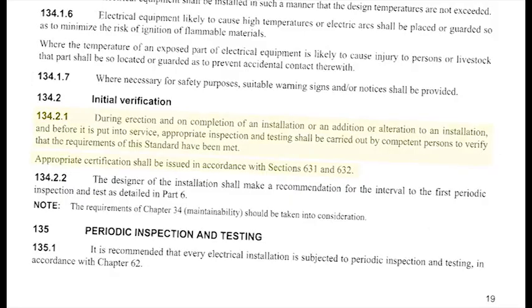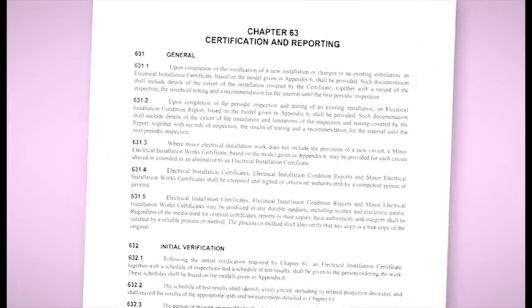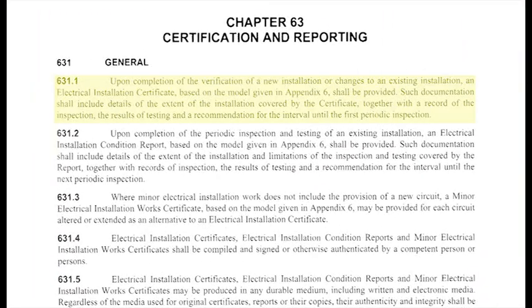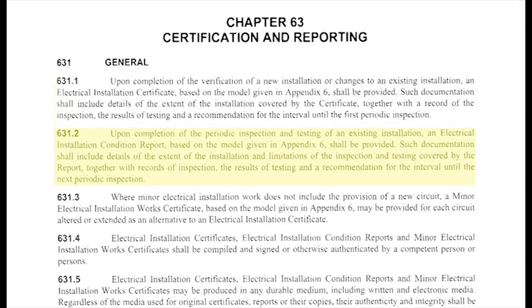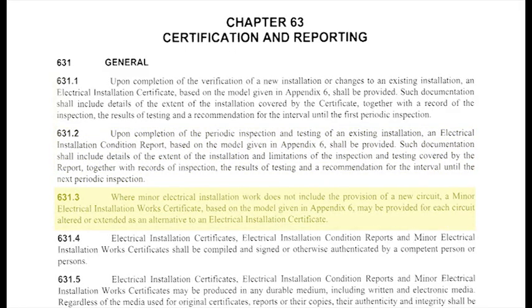First and foremost, certification is a fundamental principle in the regs, required by Regulation 134.2.1, which requires that after initial verification, appropriate certification shall be issued. In Chapter 63, Certification and Reporting, Section 631 details the requirements for electrical installation certificates, electrical installation condition report, and minor electrical installation work certificates. I'll summarise the requirements in simple terms.